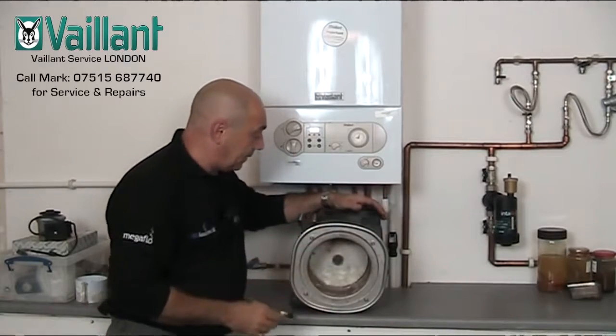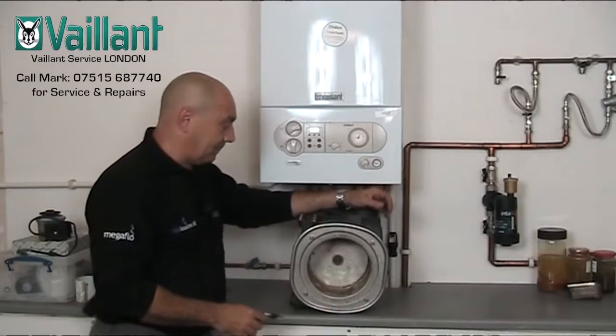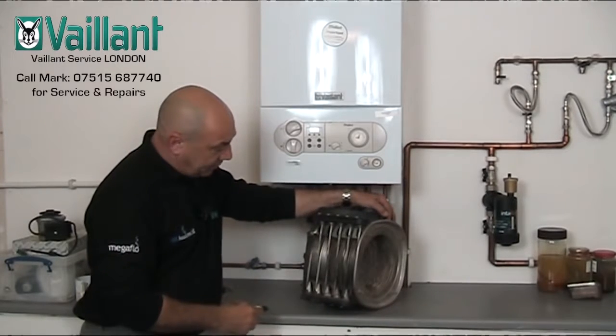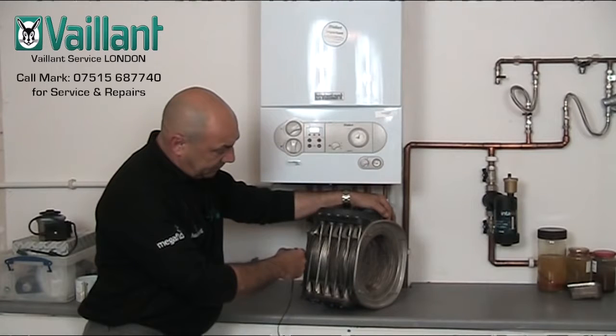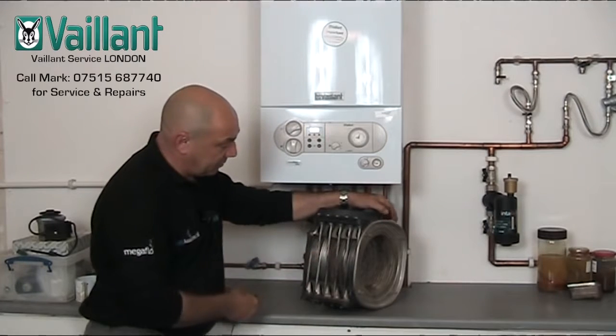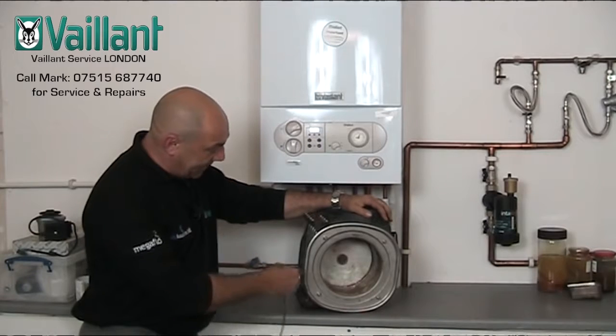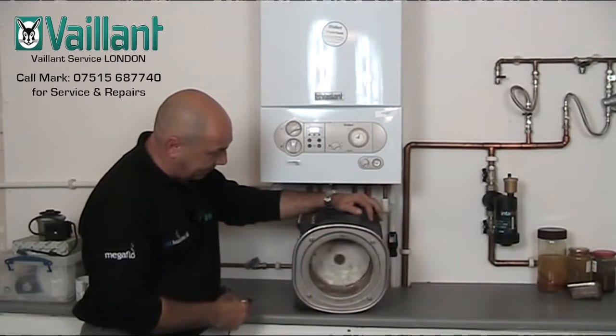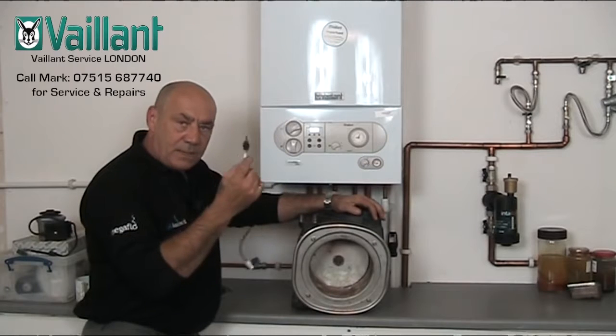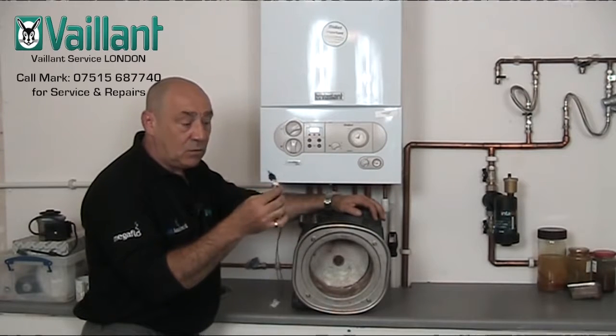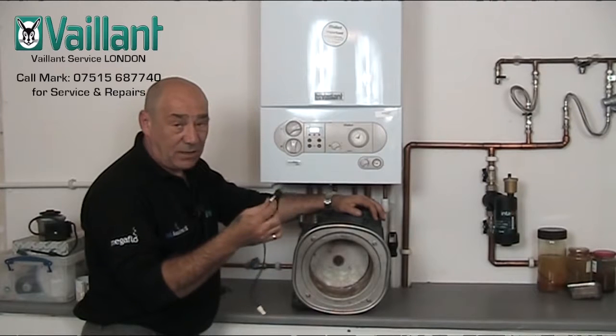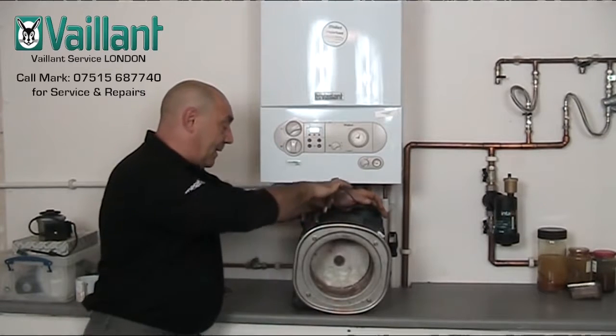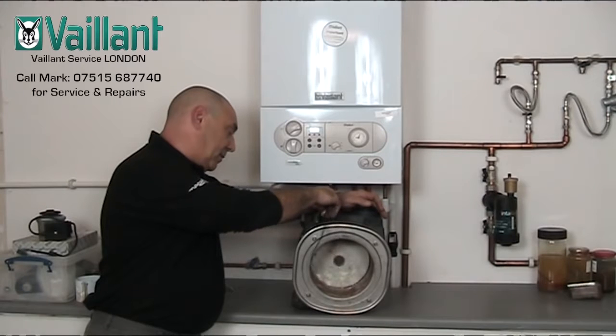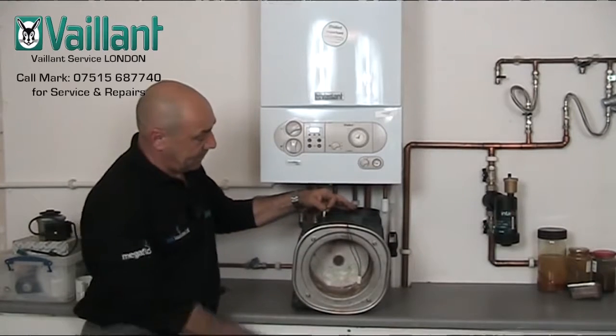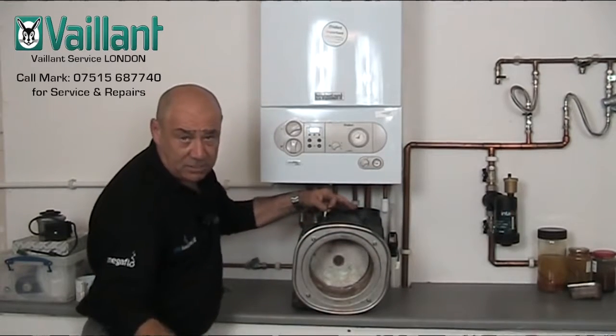But there you go. This is a main heat exchanger out of a Vaillant ecoTEC boiler. It consists of a plastic shroud with a multiple coiled heat exchanger inside of stainless steel tubing, and then we have an air gap between the tubing and the plastic shroud outside. This is a thermal link, or what we would call years ago, or I would basically call, an overheat thermostat or trip, and that is situated in the top of the heat exchanger in here, like that. Well, sort of like that, okay? And then the leads come down and they go down into the printed circuit board, and that's what controls it.